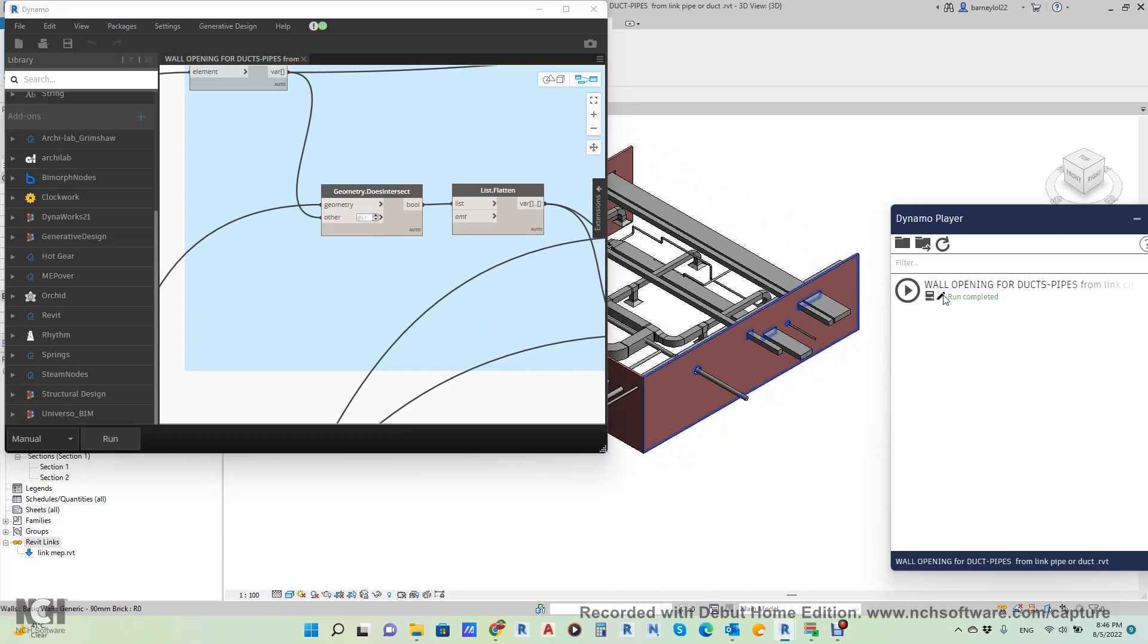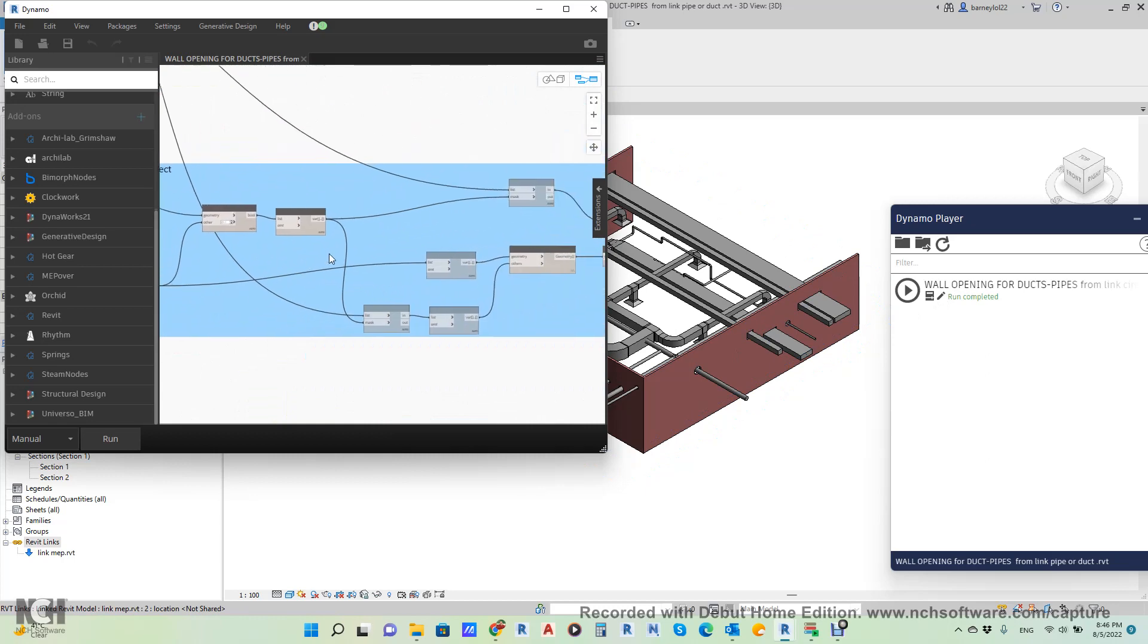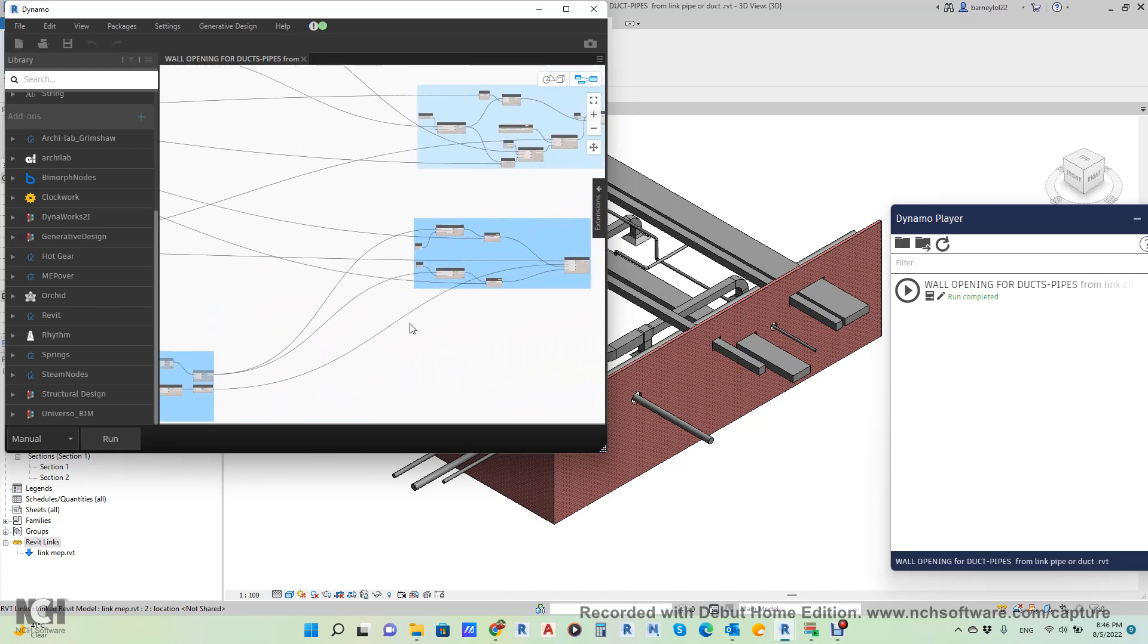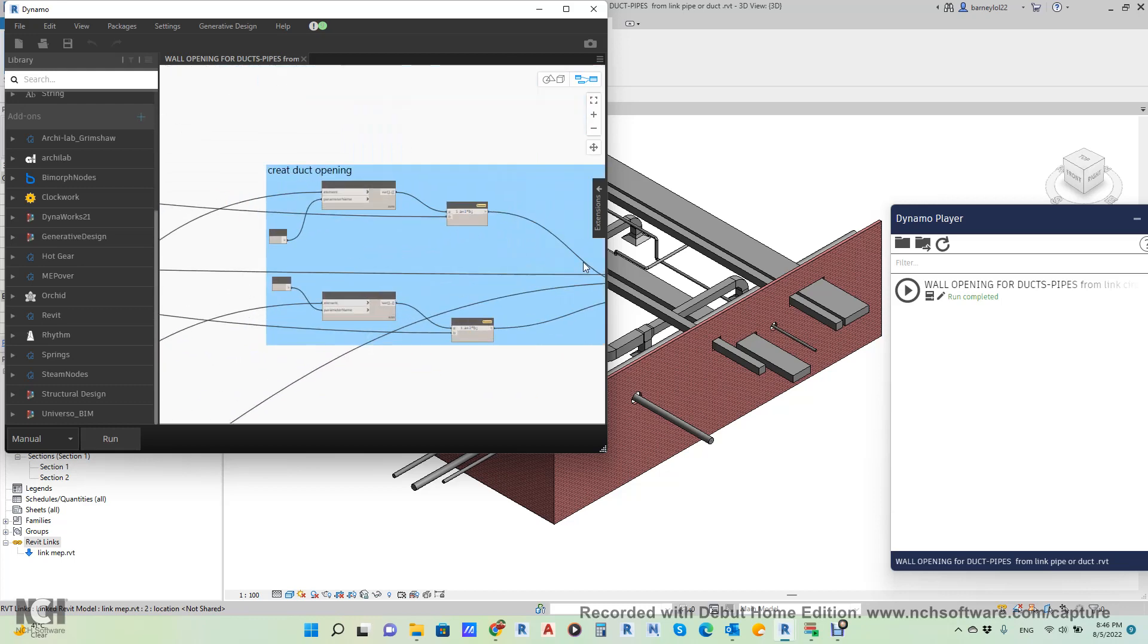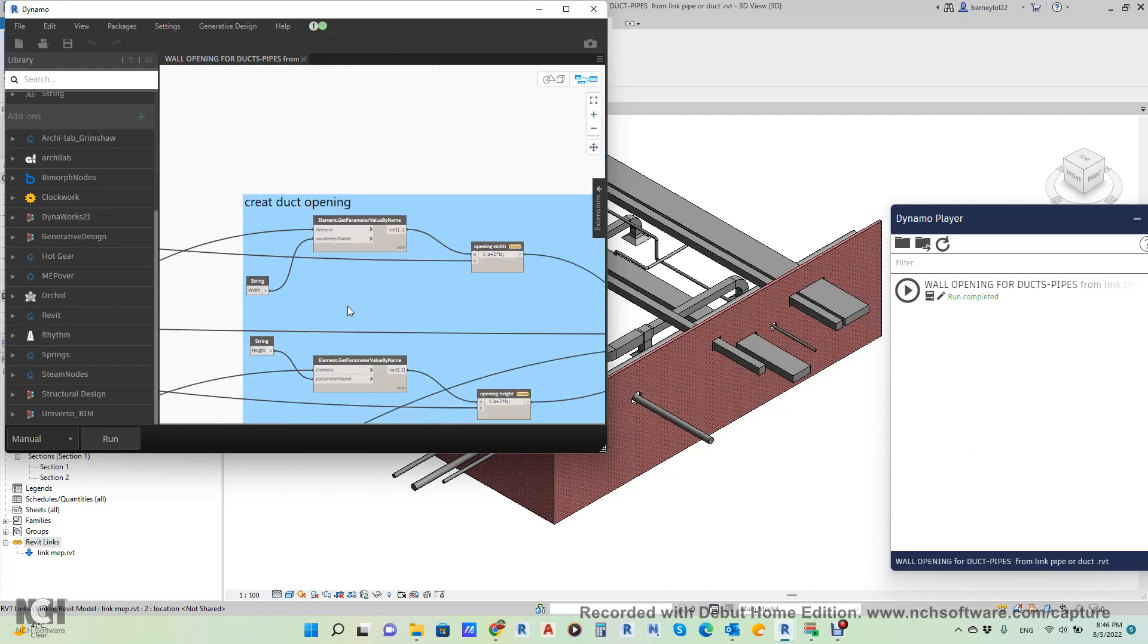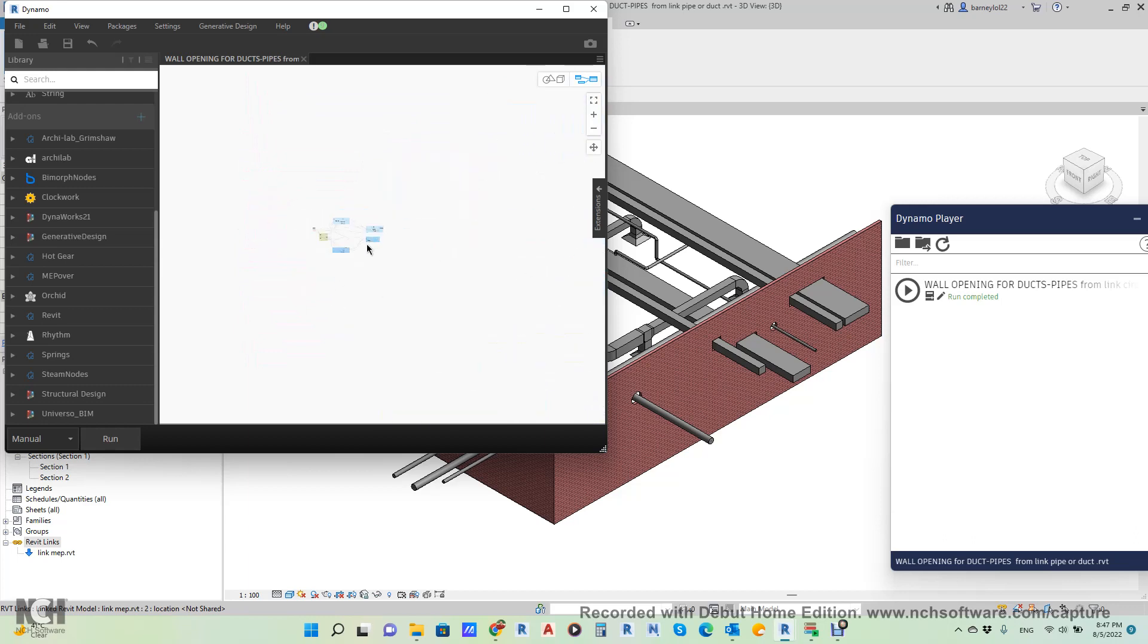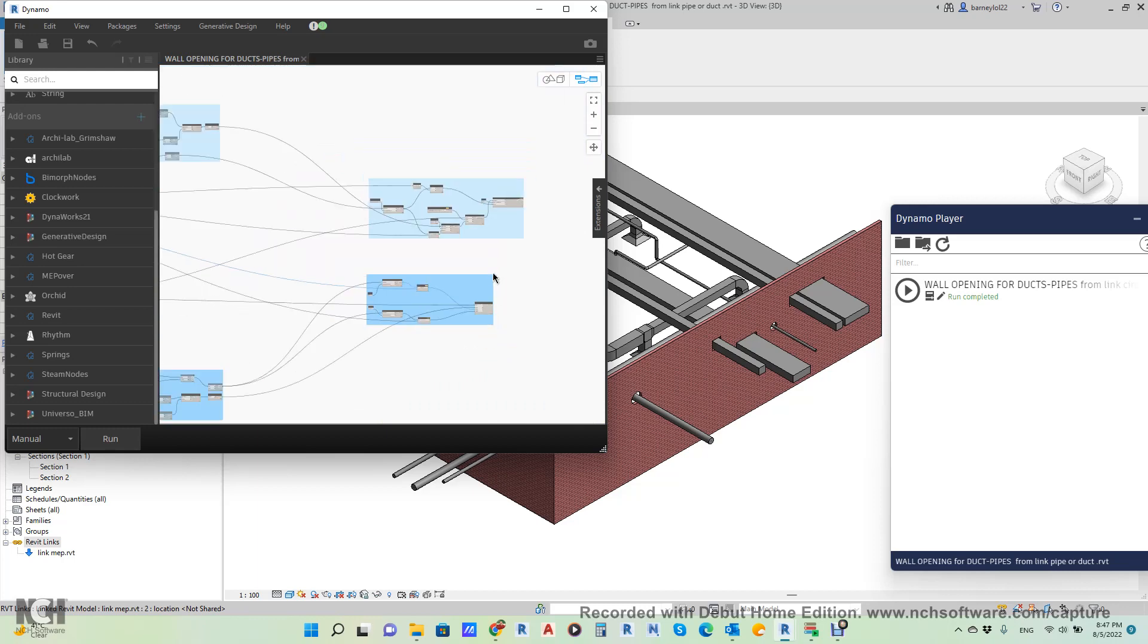And then he will filter it, and then he will make the centroid of the intersection here. And then he will create an opening. This opening diameter will be depending on the duct size—the width of the duct and the height of the duct. He will collect it from the duct for the designated duct intersecting with this wall, and then he will add the insulation. This will go to the insulation here, which we will choose. And then he will create finally the wall. This is how this works, and similar concept for the pipe. This is how the Dynamo works from inside.